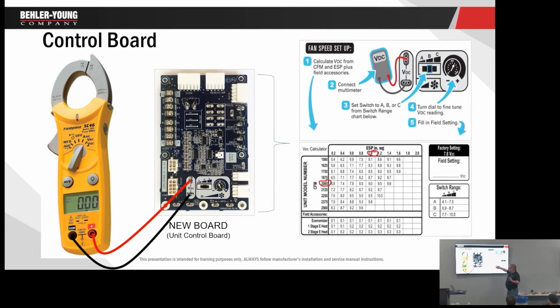This is DC voltage. Now when I pass that board around, there's what looks like 2 female spade connectors right here. And they're marked VDC, volts DC. If you take your meter, put it on DC. This is important because on DC we don't have hot and neutral, we have positive and negative. So positive is red, black is negative. If you reverse your leads, you're going to get a negative reading. Red lead on positive, black lead on negative.